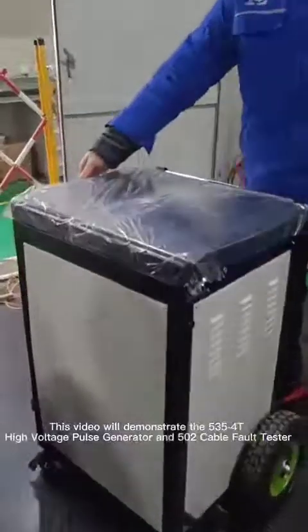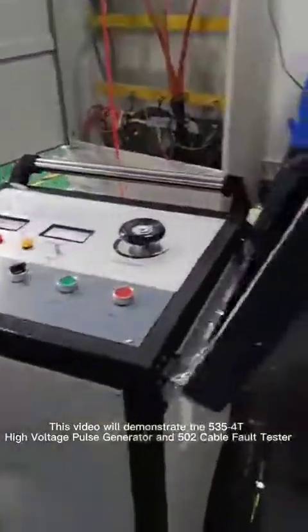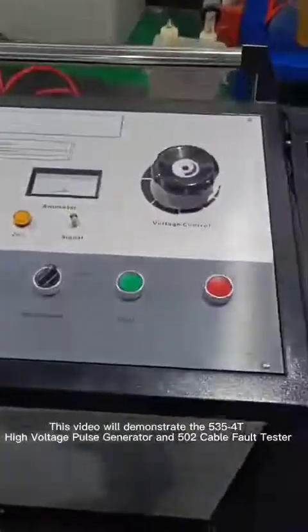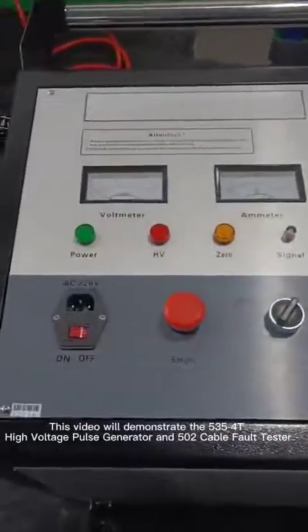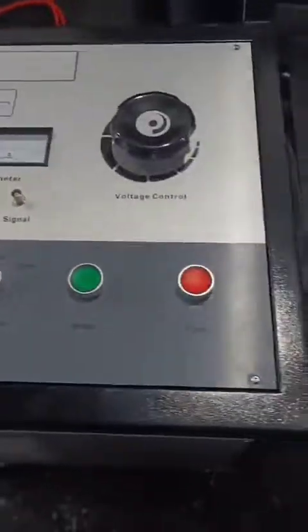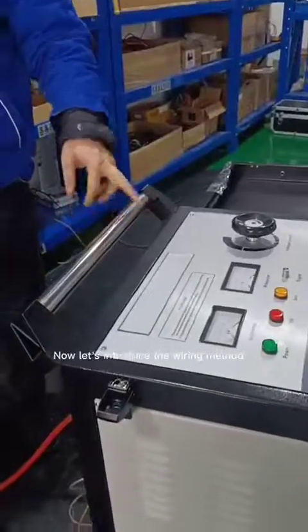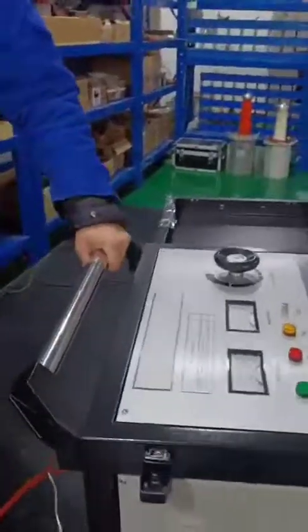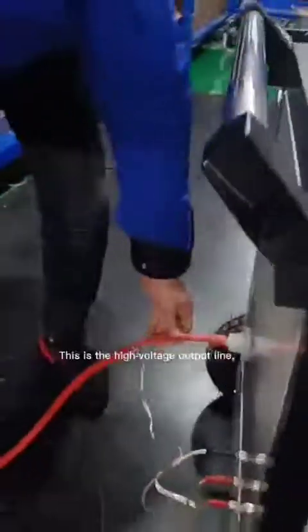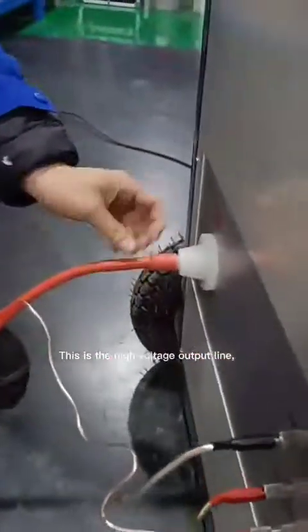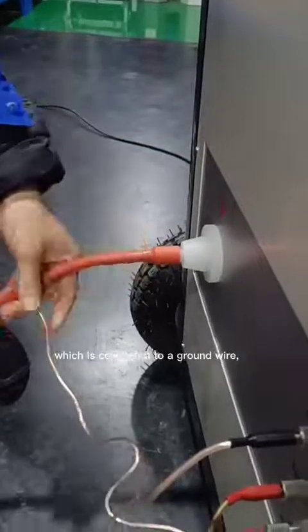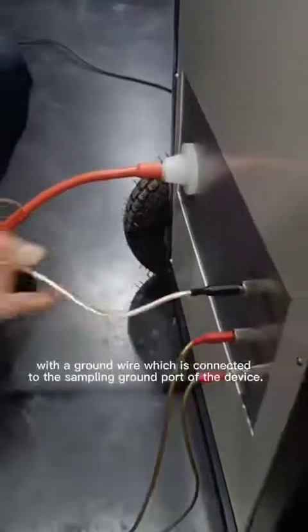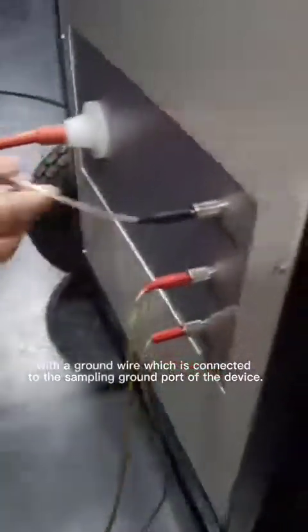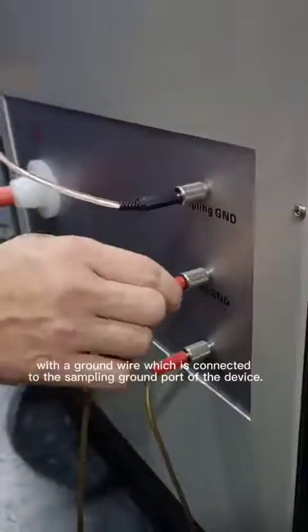This video will demonstrate the 5354T high voltage pulse generator and 502 cable fault tester. Now let's introduce the wiring method. This is the high voltage output line, which is connected to a ground wire, with a ground wire which is connected to the sampling ground port of the device.